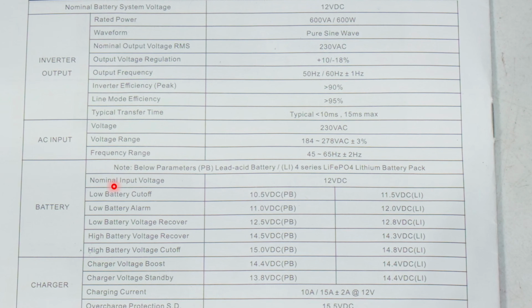And I just want to show you another specification, and that is the battery cutoff voltage. The inverter is designed in such a way that if the battery voltage gets below 10.5 volts, and that's for lead, because this inverter can work with a lead acid battery or lithium ion battery. So the low voltage cutoff for lead is 10.5 volts, and for lithium it is 11.5 volts. This is important in determining the maximum current rating, which is important in the design of the protection system.